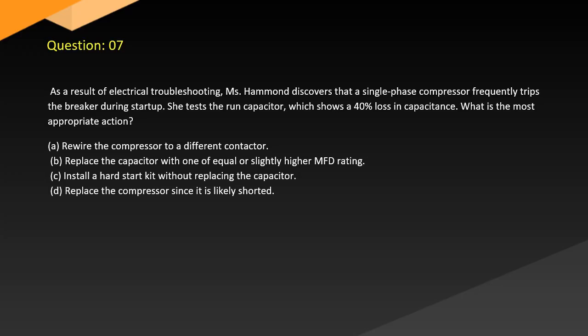Question 7. As a result of electrical troubleshooting, Hammond discovers that a single-phase compressor frequently trips the breaker during startup. She tests the run capacitor, which shows a 40% loss in capacitance. What is the most appropriate action? A. Rewire the compressor to a different contactor. B. Replace the capacitor with one of equal or slightly higher MFD rating. C. Install a hard start kit without replacing the capacitor. D. Replace the compressor since it is likely shorted.